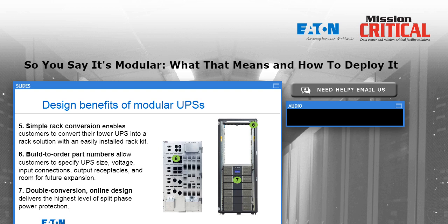This particular UPS is a double conversion design. Most UPSs in this range of around 2 to 12 kilowatts are going to be double conversion UPSs, and they will typically be single phase or split phase power protection.